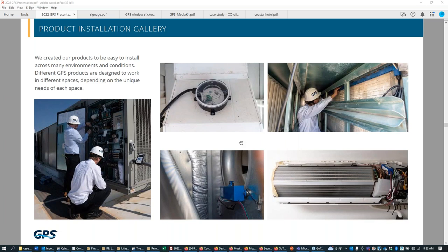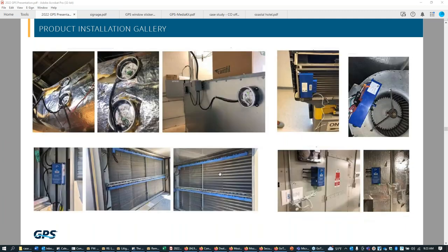These are some installed photos. This is a single duct mounted application. This one is on an evaporator coil. This is a fan mounted unit in the bottom center that you see. And this is good for rooftop units, things like that, where maybe you don't have access to the ductwork. When we've got a larger airflow, we can put these in parallel with one another. And that's what this represents. These duct mounted devices, the one that you see here is rated for up to 4,800 CFM. In a VAV application, I'll typically derate that to maybe 2,500 CFM to account for VAV turndown.